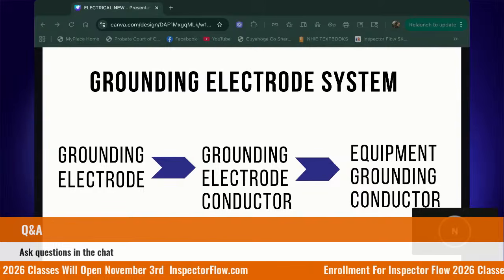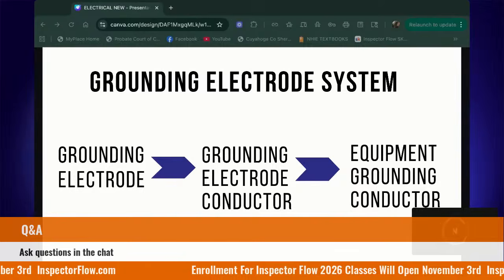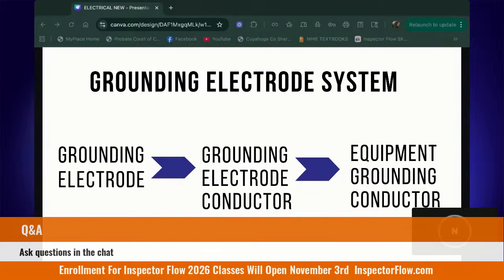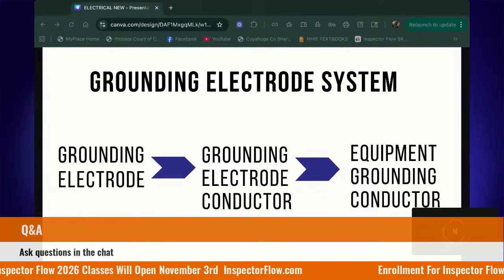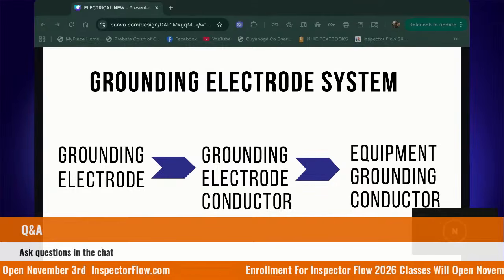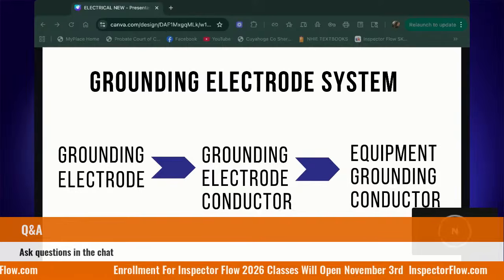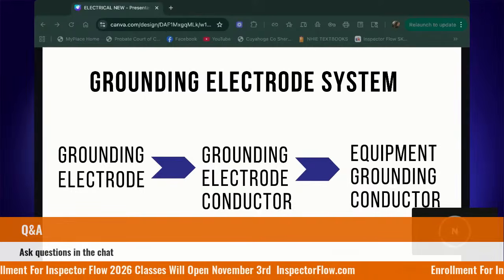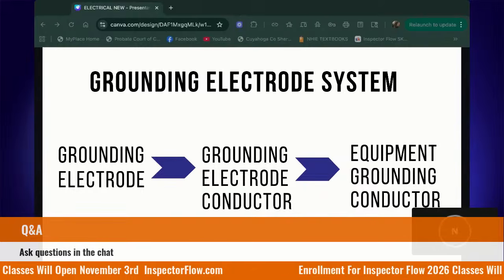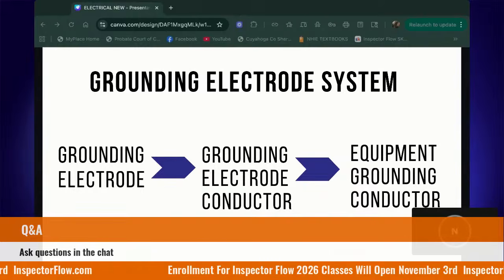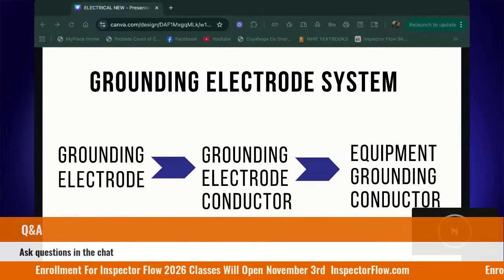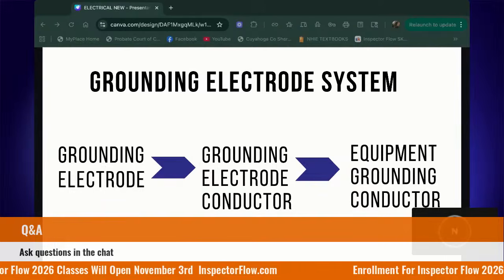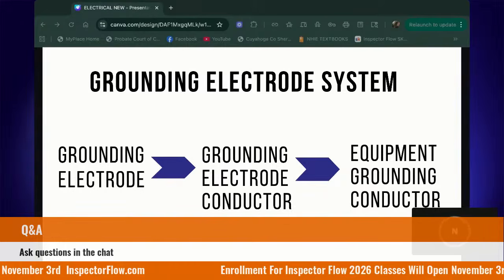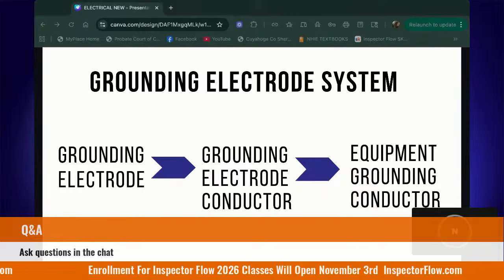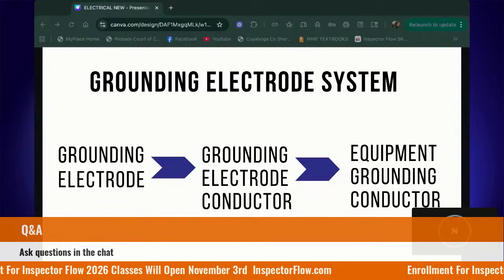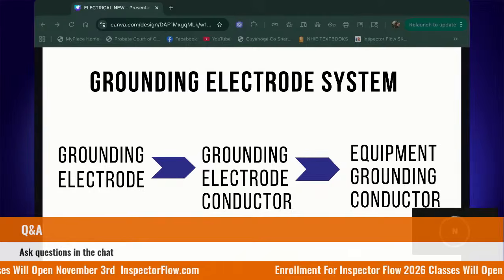Have you ever heard anybody say a ground rod? There's a ground rod there. I see a ground rod. The ground rod is the grounding electrode. It is actually in the ground. So we are connecting our home's electrical system to this ground rod outside, which is called, again, a grounding electrode. You can have different types of grounding electrodes, but the ground rod is the most common type. It's going to either be steel or copper, at least about 8 to 10 feet long, and it's driven into the ground.